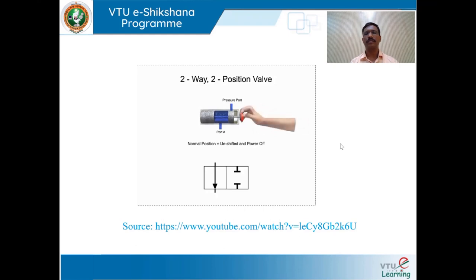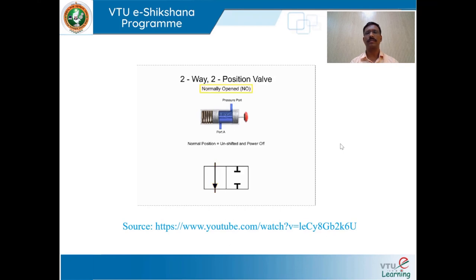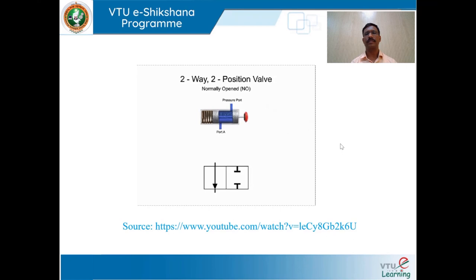The terms normally open and normally closed describe the condition of a valve in its normal position. A valve whose normal position allows unrestricted fluid flow is normally open; one that blocks flow is normally closed. A spring return valve uses a spring to return the spool to normal position after actuation. The primary actuator symbol is placed on the other end of the graphic symbol — in this case a push button.